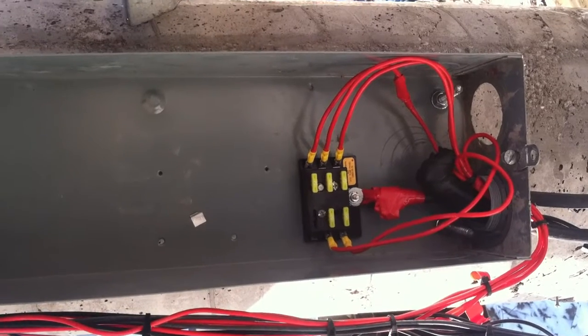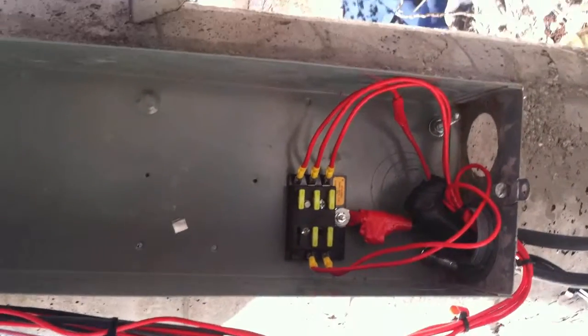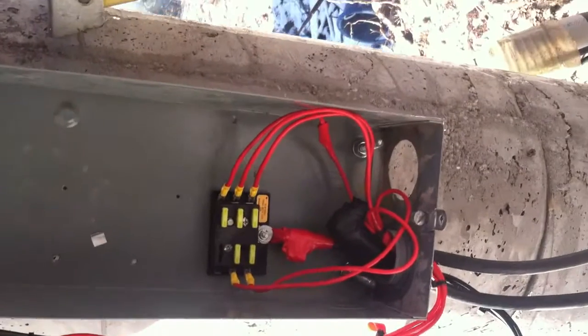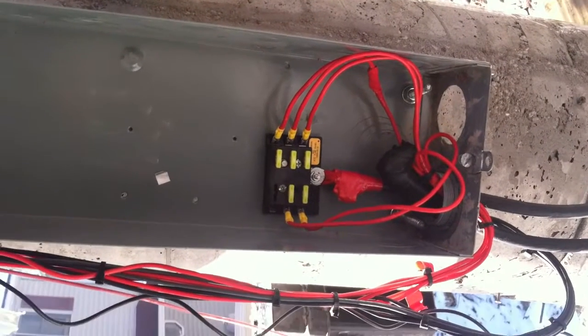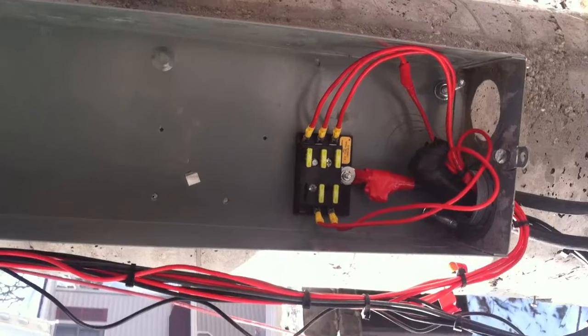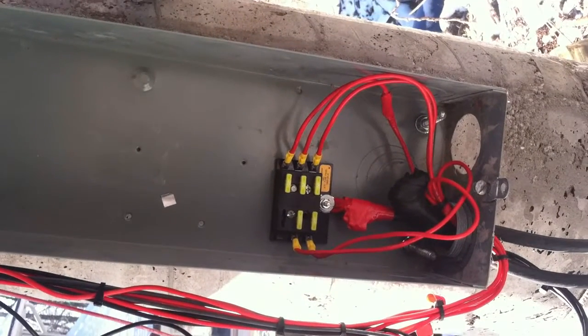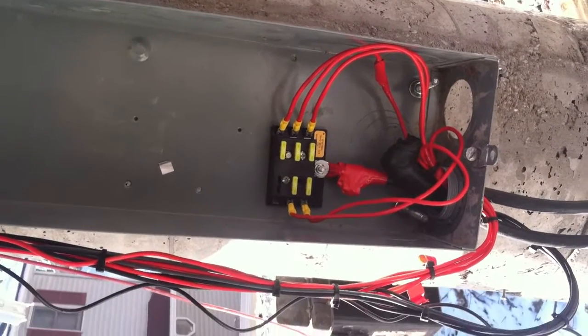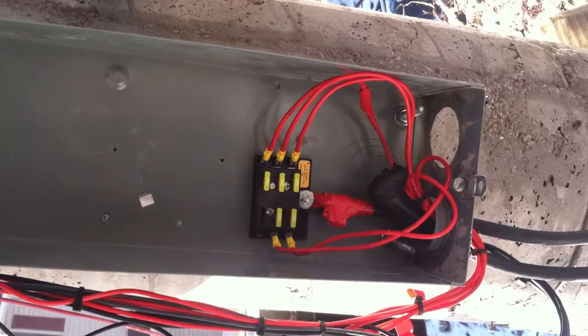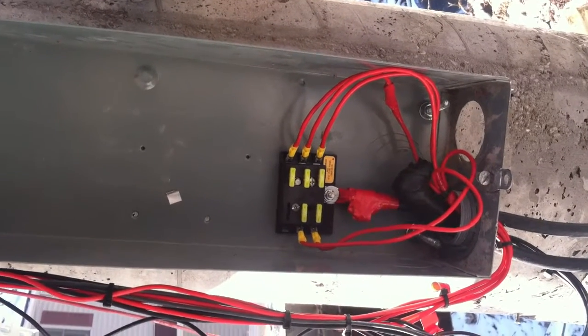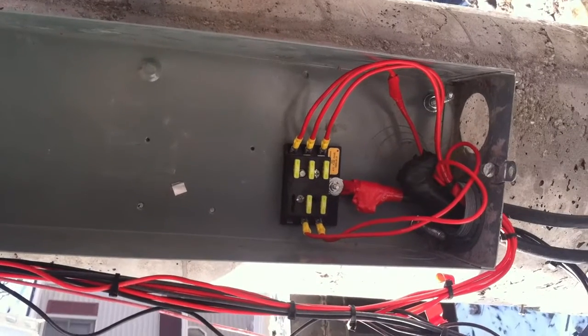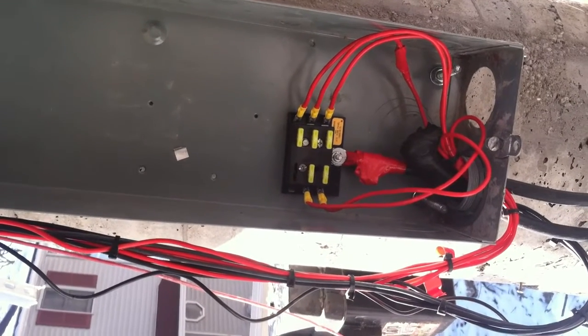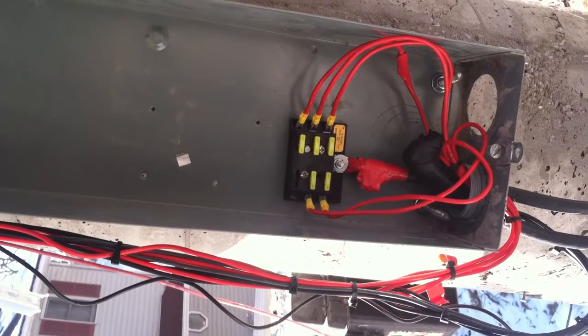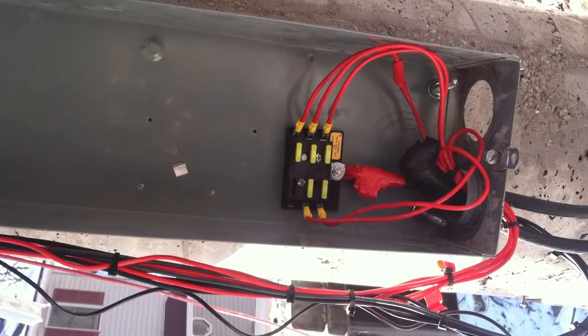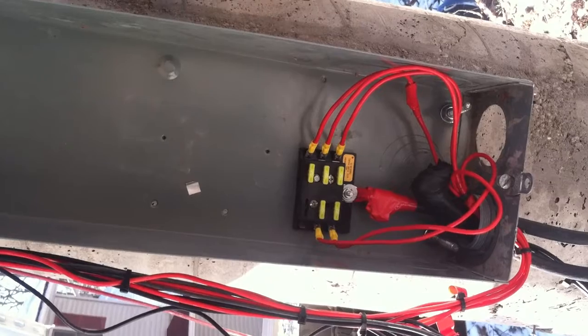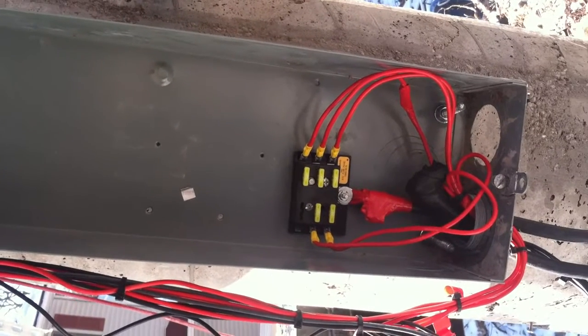So the wires are about 10 gauge, so they could handle roughly 20 or 30 amps. So you want to fuse them before 30 amps. Now each short circuit current is like 7.5, under 8 amps. So if one of them short circuits, it's going to be 8 amps. So if there's two of them in a row, that'll be 16 amps going through the wire. So you want to make sure you fuse that wire with 20 amp breakers, so in case there's a short, it's not going to fry the wires.